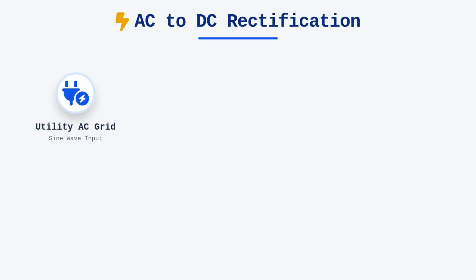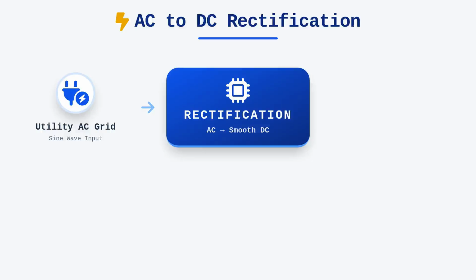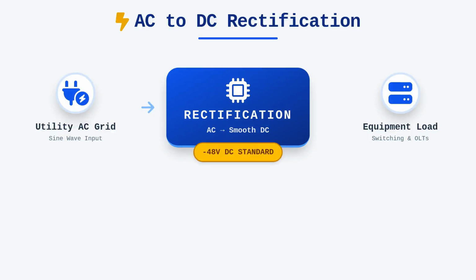Moving from utility AC to the internal environment of a central office requires an understanding of the rectification process. Telecommunications equipment, particularly switching infrastructure and optical line terminals, has historically relied on negative 48-volt direct current power plants. This standard exists because DC provides superior stability and allows for seamless integration with battery backup systems, ensuring that central offices remain operational during utility outages without the split-second gap inherent in some AC switching mechanisms.